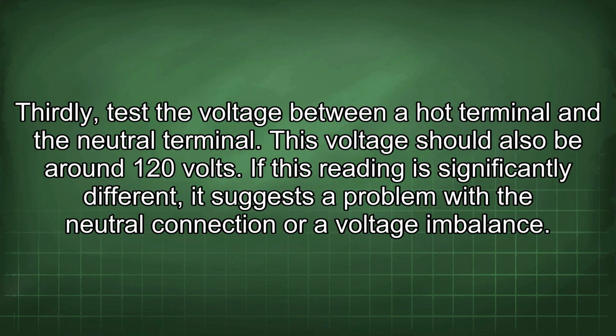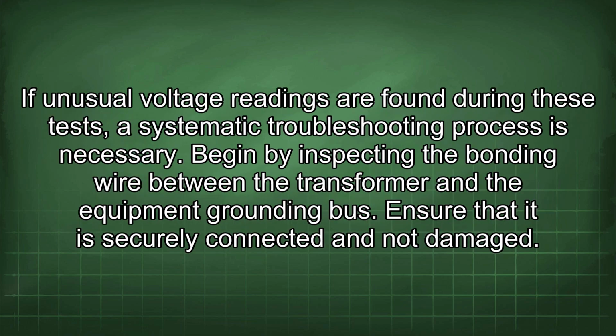Thirdly, test the voltage between a hot terminal and the neutral terminal. This voltage should also be around 120 volts. If this reading is significantly different, it suggests a problem with the neutral connection or a voltage imbalance. If unusual voltage readings are found during these tests, a systematic troubleshooting process is necessary.